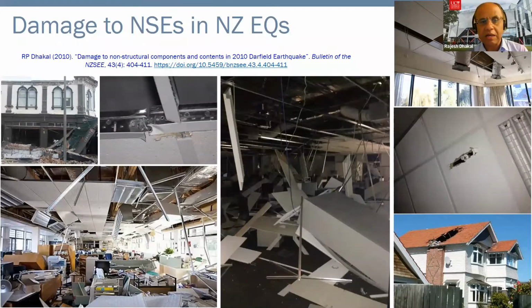One example is the middle figure there on the right. You can see a sprinkler head tearing through a ceiling panel, and quite a large length of the ceiling panel was torn off. Based on our mechanics theory, we can never get an estimation of that level of damage, that extent of tearing through, from the interstory drift in a building in a small earthquake like the Seddon earthquake of 2013.